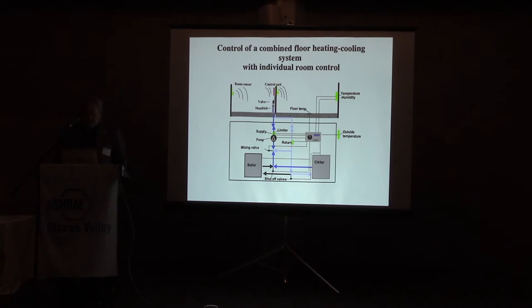Now, some people will say that these systems are very slow, because even if you have floor heating in the screed, you have a certain mass, especially if you have what they call a TABS system, where you have a whole concrete slab to control. But here you have to look at what it is you want to control for. If you want a space where for 2 hours in the morning you want 20 degrees and then 2 hours later you want 25, then it's not the system to use, because it's very slow. Then you have to warm up the whole screed or concrete.